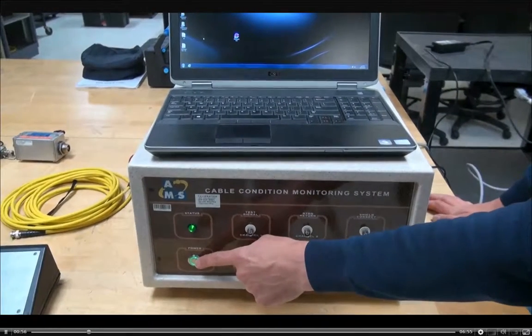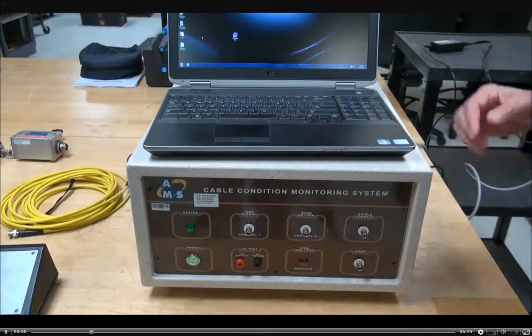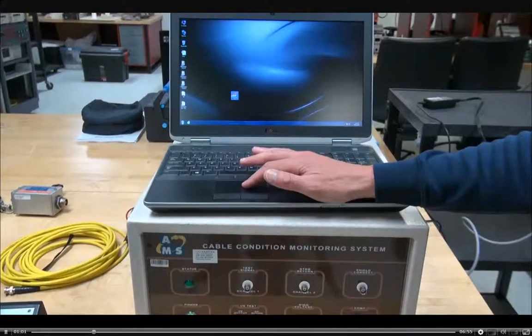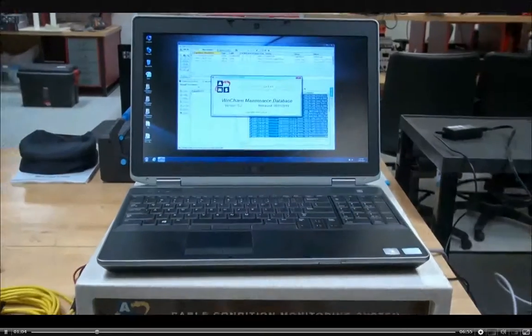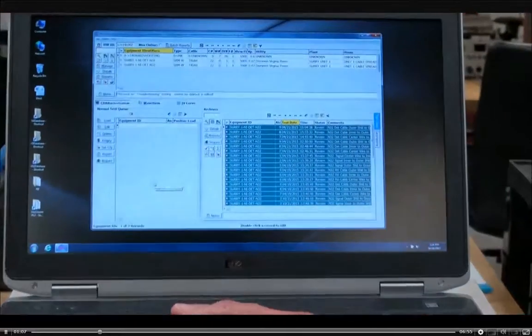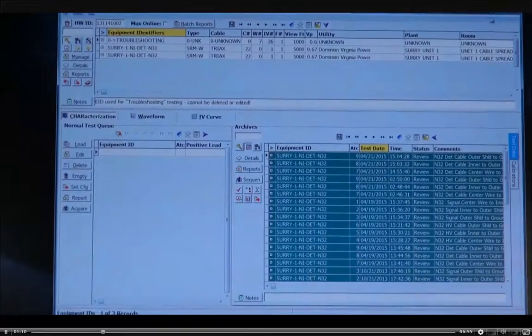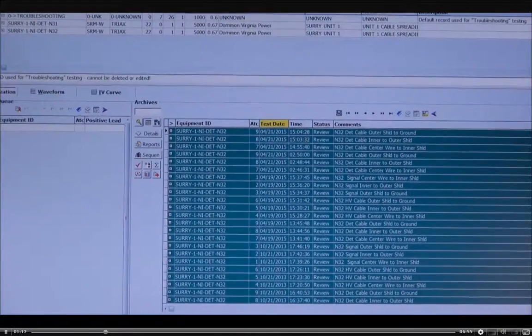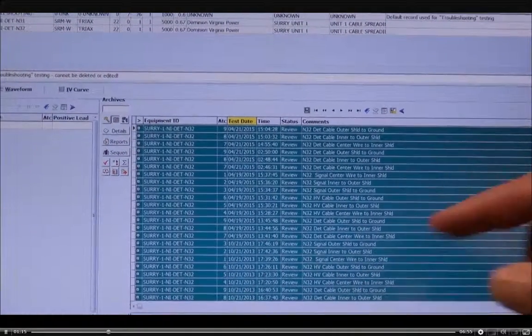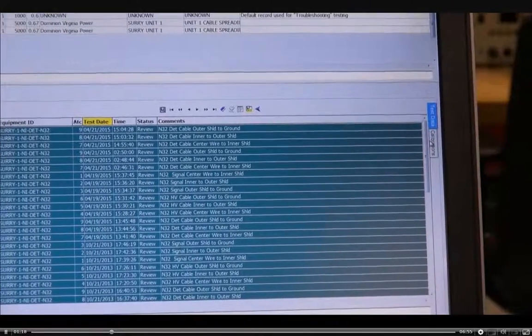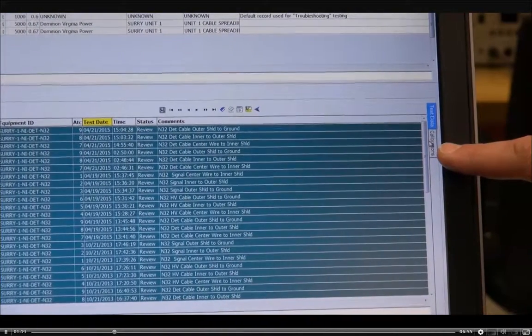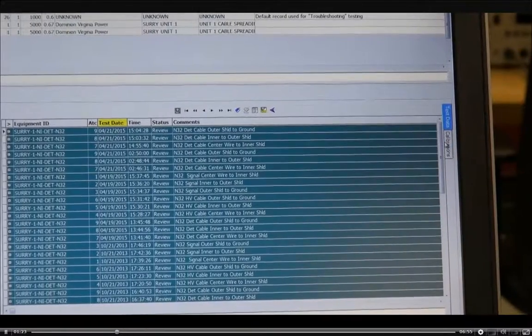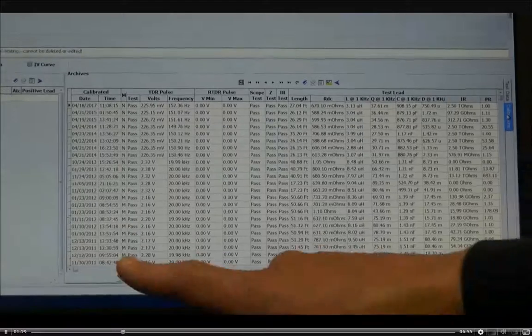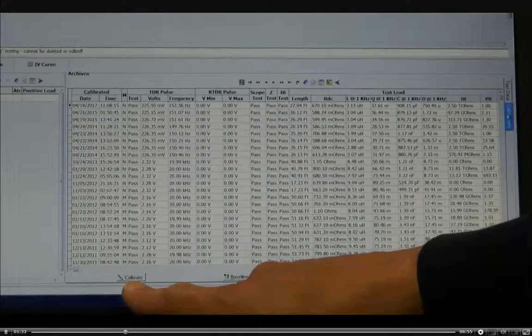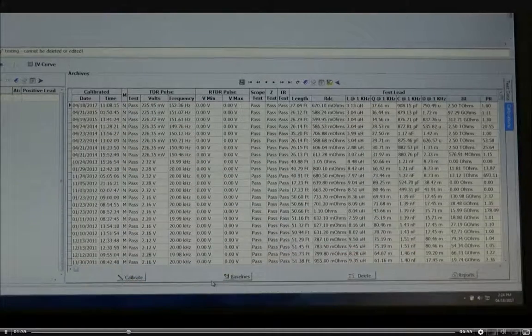We turn on the CHAR system. And once everything is up and running, we want to go to the CHAR version 5.2. And the first thing we'll want to do is over on the right hand side here is a calibrate. Right here, calibrations tab, right here. So I hit the calibrations tab. These are all the previous times that the unit has been calibrated. Down at the bottom of the screen right here is the calibrate button. We'll hit that and give it a fresh calibration.